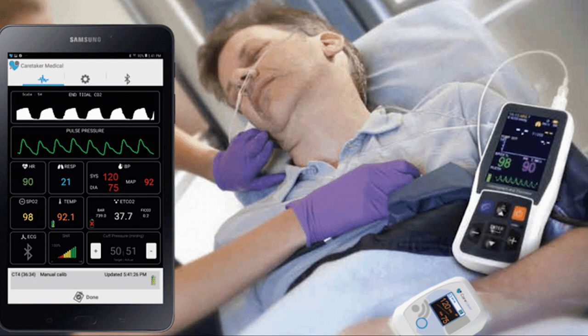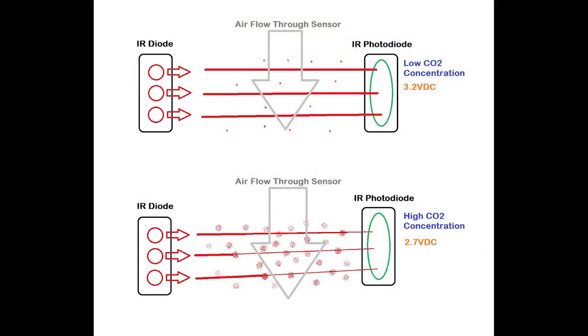Capnography shows instant patient reaction to drug therapy, sudden changes in health conditions, and the patient's reaction to mechanical ventilation settings. EtCO2 sensors consist of infrared light-emitting diodes which shine across a gas sample exhaled by the patient. That light is measured by a photosensor on the other side of the gas sample. CO2 naturally absorbs infrared light, so the more infrared light that's measured means a lower amount of exhaled CO2, and inversely, the lower the amount of IR light means the higher amount of exhaled CO2.